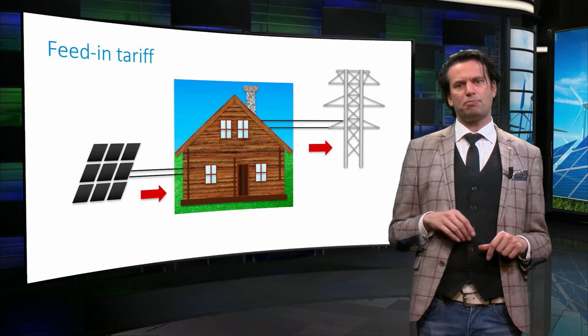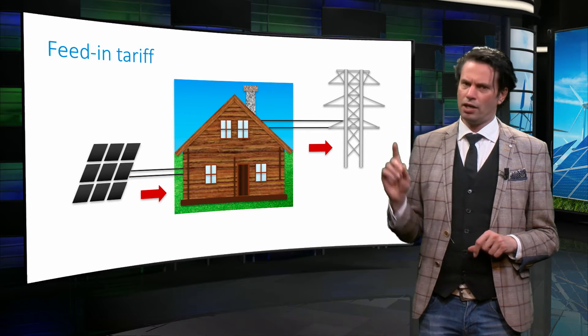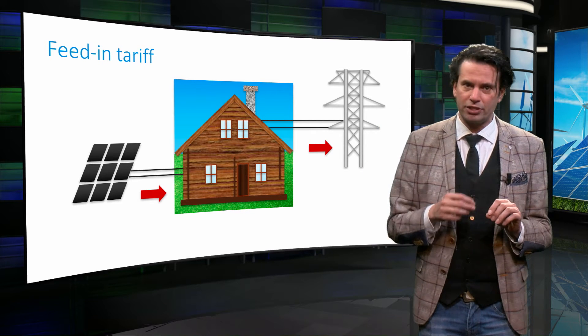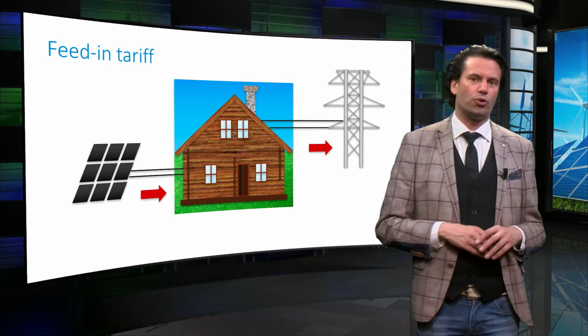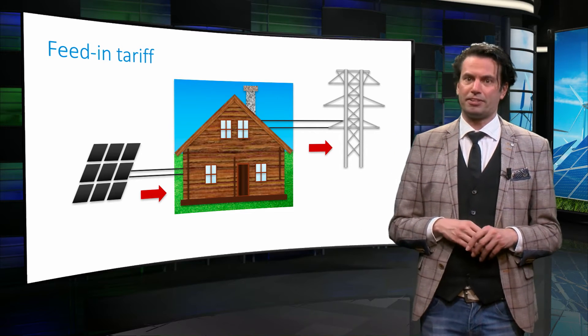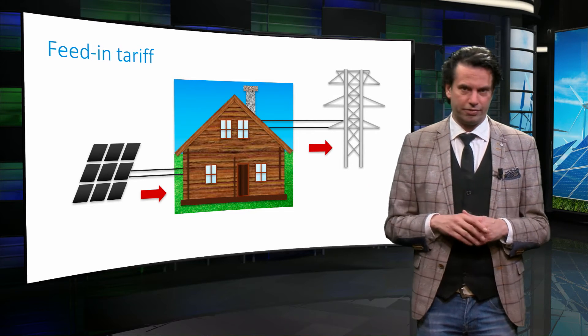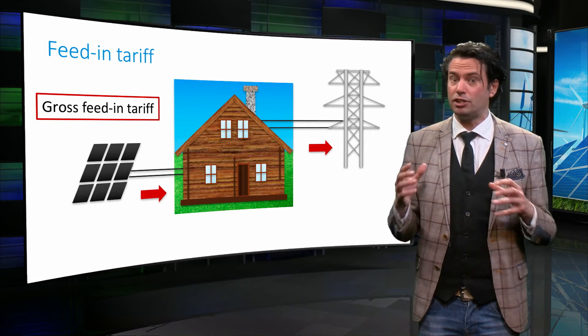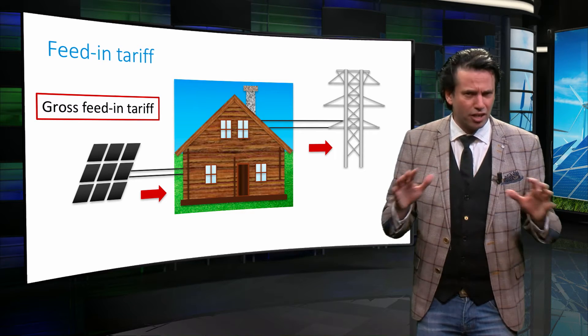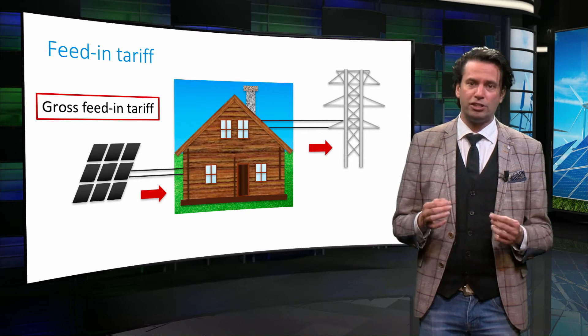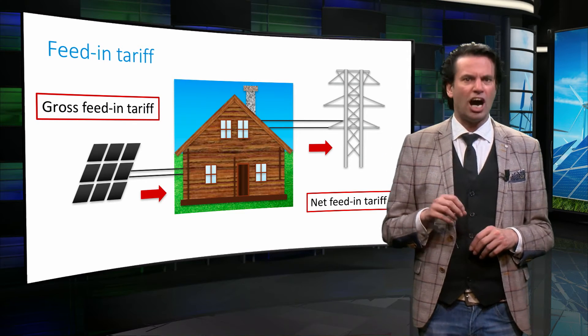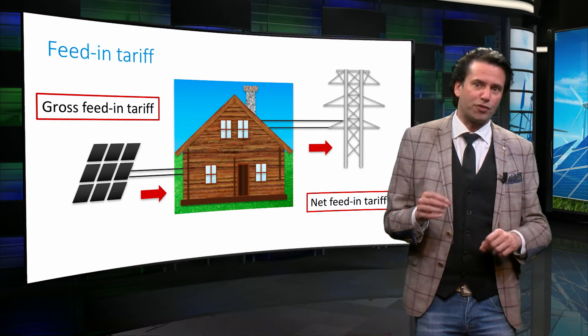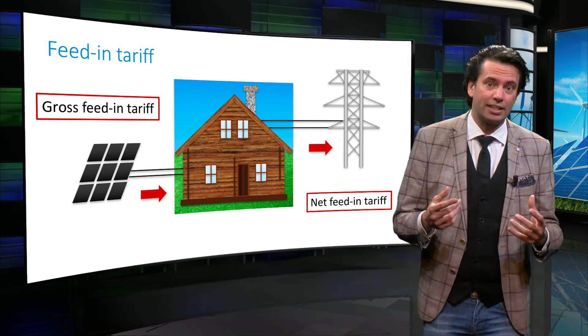Let us briefly discuss the concept of feed-in tariffs in PV systems. The feed-in tariff is the rate that a consumer is paid for the electricity that a grid-connected PV system contributes to the local grid. There are two kinds of feed-in tariffs, namely the gross and net tariff. The gross feed-in tariff is the amount paid for all the electricity generated by the PV system, regardless of the electricity consumption of the PV system owners. The net feed-in tariff is a higher rate, paid for the surplus electricity fed into the grid after subtracting the domestic consumption.